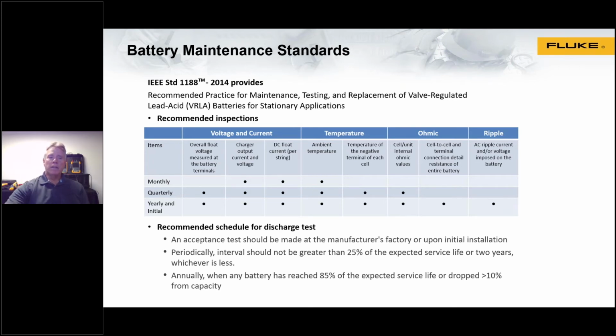So you can see that the columns on the top tell you what measurements need to be made: voltage and current measured at the battery terminals, charger output, charger current, DC float voltage, DC float current, temperature, also ambient temperature, but also temperature at the negative terminal of each cell is recommended to be measured. Internally on the battery, health measurement, which we're going to be exploring more, would be cell internal ohmic or resistance measurement, and then also cell to cell connections. And then also if we have batteries strapped together, we want to measure that strap resistance. And then also, as we just spoke about, very important to make sure that your ripple voltage is not excessive. Otherwise, that'll shorten the life of the battery.